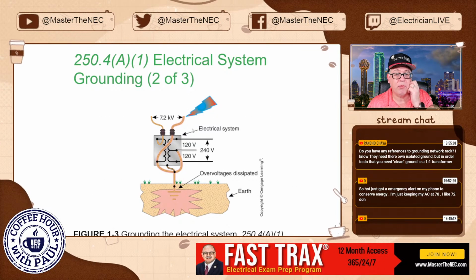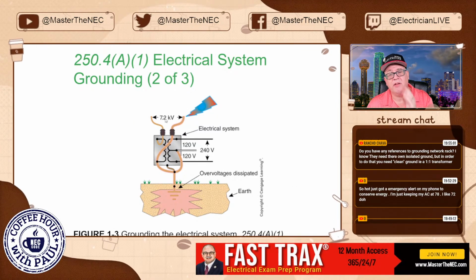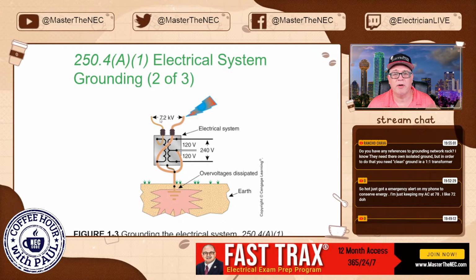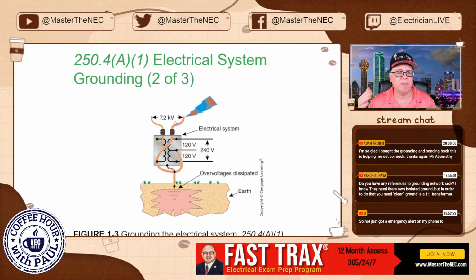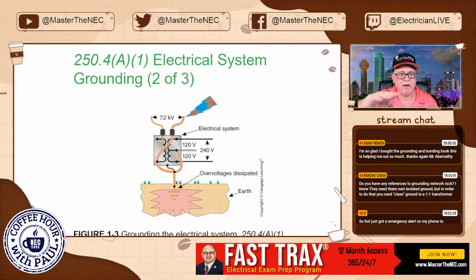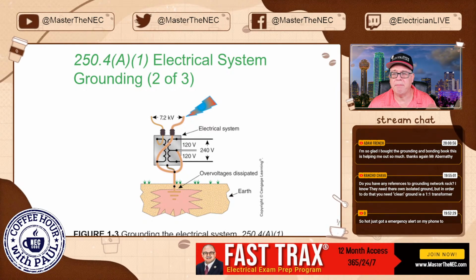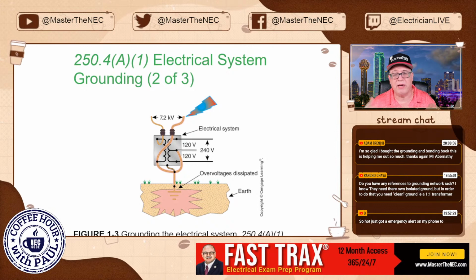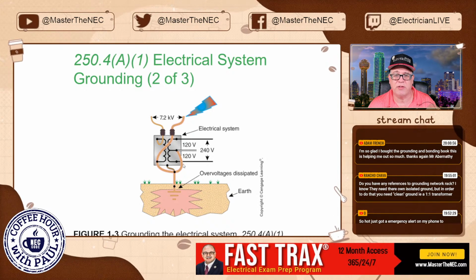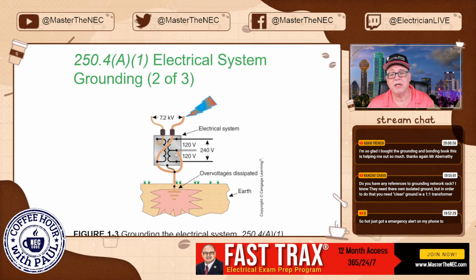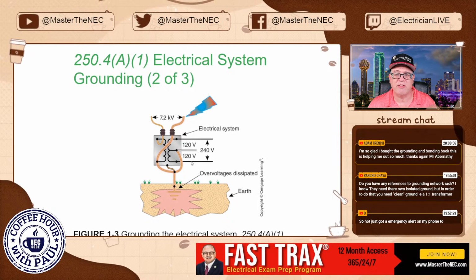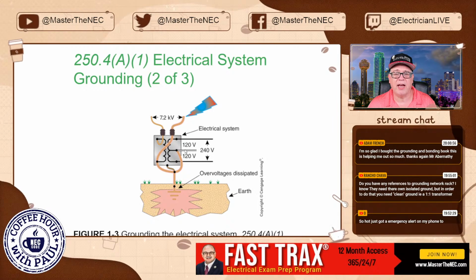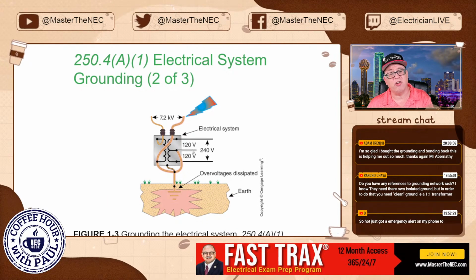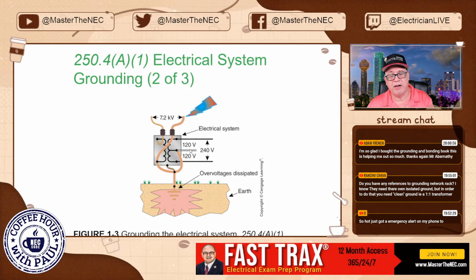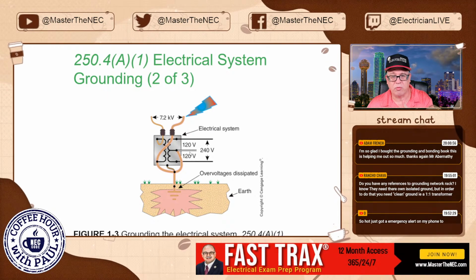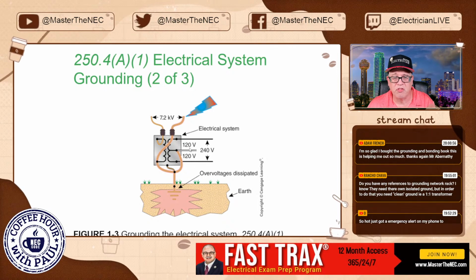This is an example, and of course, good timing. This is an example of a utility transformer. Here's 7.2 kV, might be running down through your neighborhood, and it's going to hit a transformer. Now it's going to drop down to your house. This is typically what you would see. Here you've got your two phase conductors and your grounded conductor. In this case, it is a neutral, because here to here and here to here are neutral. 120 here, 120 here, 240 between them. So this is a neutral system.